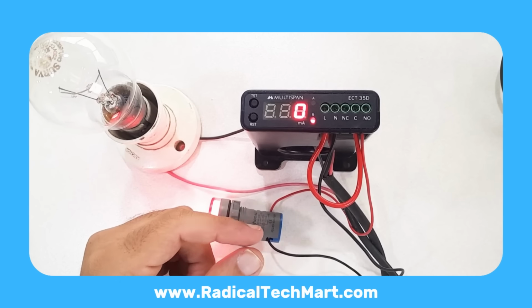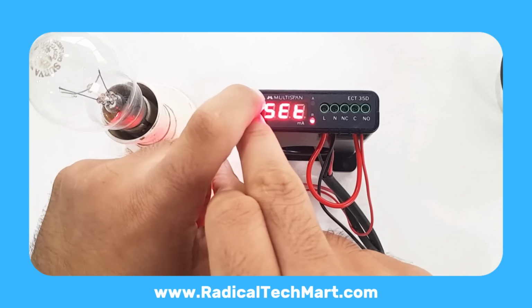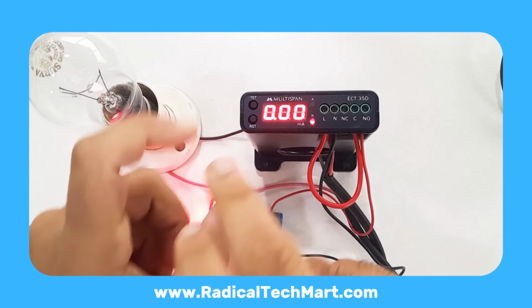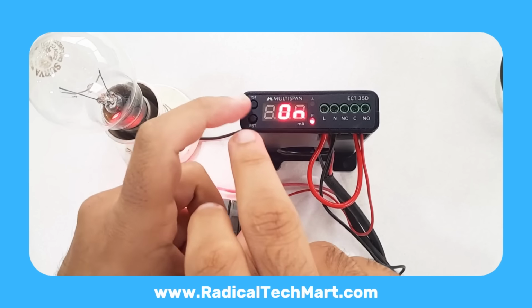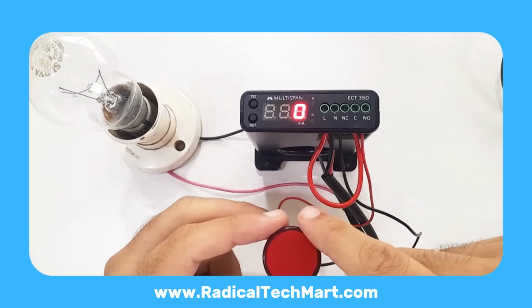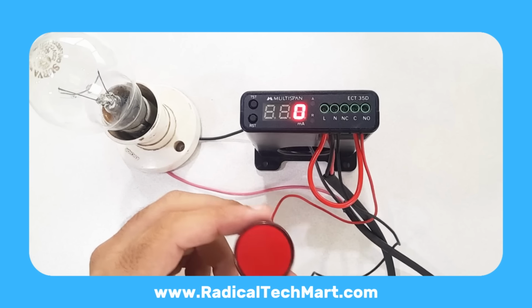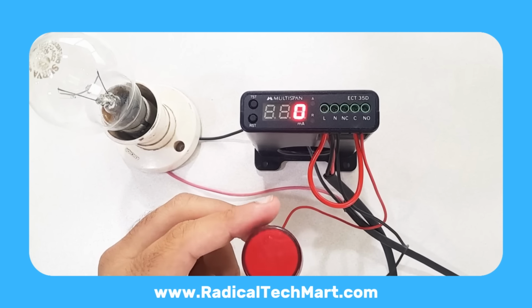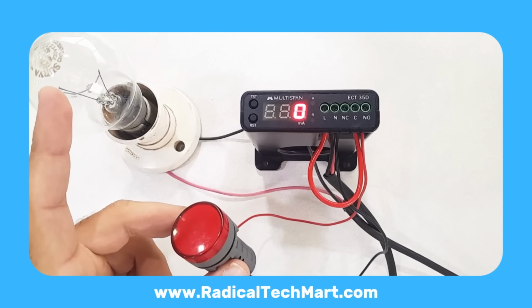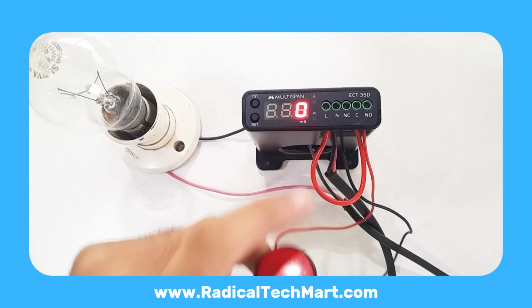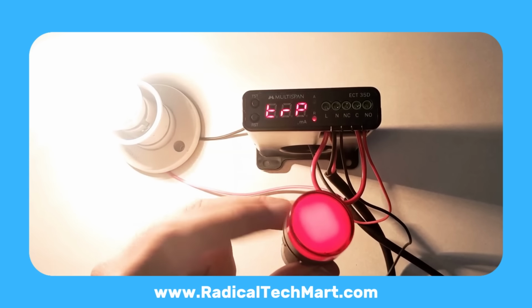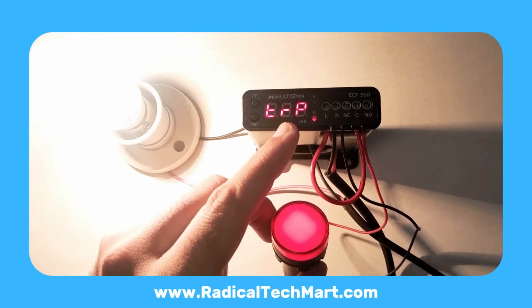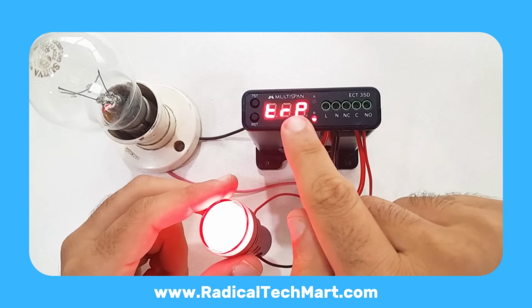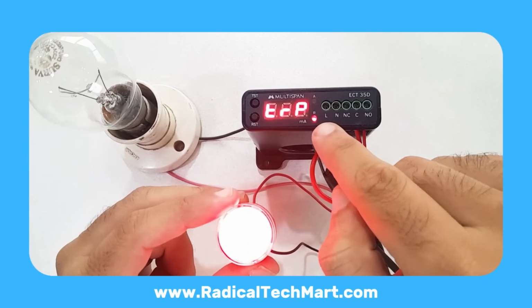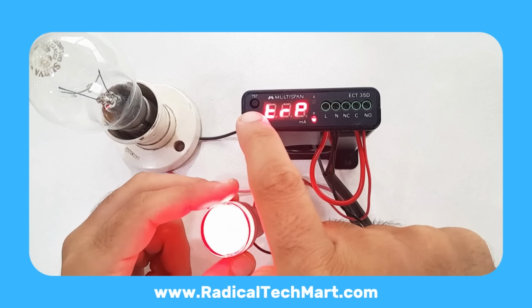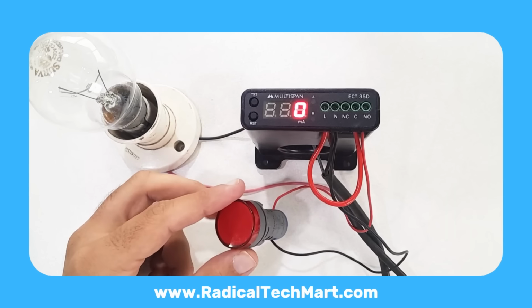Now, if your system uses an MCCB shunt or you want the relay to energize on fault, go to settings again. At relay fault mode, change from off to on, and exit. Now, when leakage occurs, for example, when I turn the bulb on again, the relay LED turns on, showing the relay has energized for tripping. The display again shows the leakage current value and the trip indicator appears. To reset it, simply press and hold reset. Everything returns to normal and the relay LED goes back to its standby state.